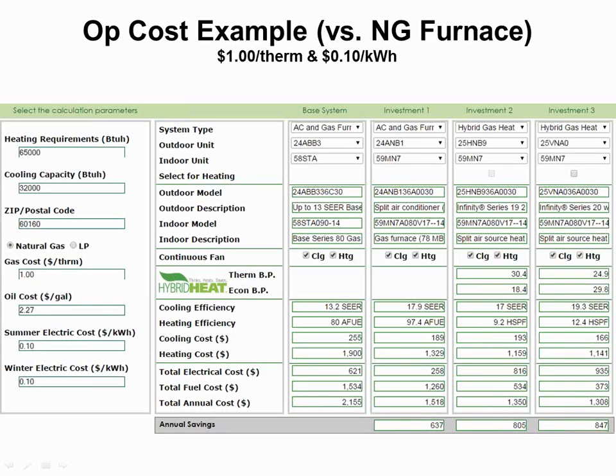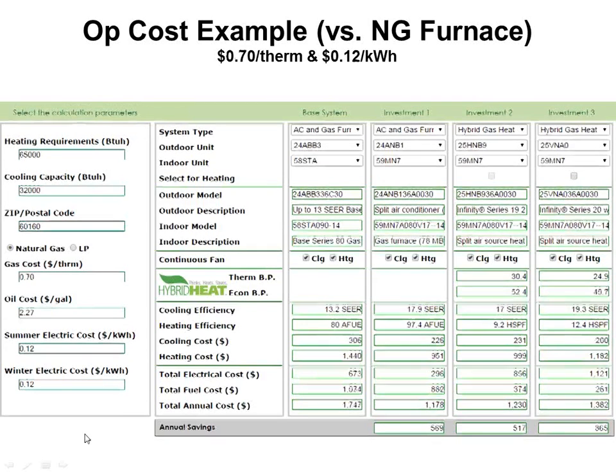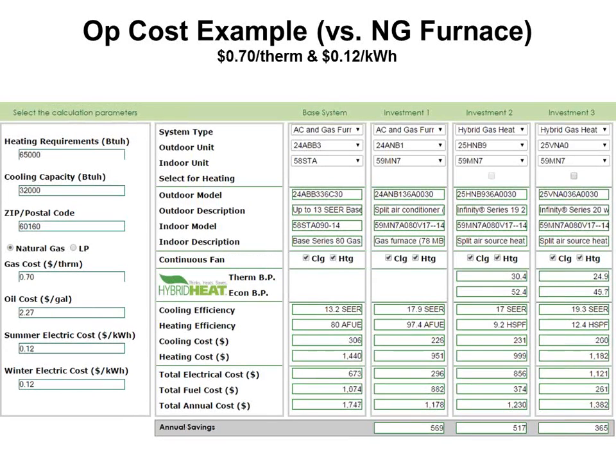If my utility costs are even lower for gas than they are, like they are now, 70 cents a therm, and a little higher for electric, 12 cents a kWh. So this is like right now, today, you can see what happens. The heat pump doesn't even pay for itself at all. So if you have natural gas available to you at 70 cents a therm, you should be using natural gas all the time and don't even waste your time with the heat pump. Now, if gas costs go back up, then the math changes and the heat pump makes sense, right?